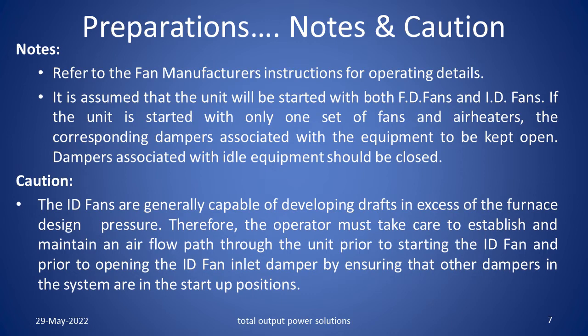You must refer to the fan manufacturer instructions for operating details of fans. It is assumed that the unit will be started with both FD fans and ID fans. If the unit is started with only one set of fans and air heaters, the corresponding dampers associated with the equipment should be kept open. Dampers associated with idle equipment should be closed. The ID fans are generally capable of developing drafts in excess of the furnace design pressure. Therefore, the operator must take care to establish and maintain an air flow path through the unit prior to starting the ID fan, ensuring that the other dampers in the system are in the start up positions.